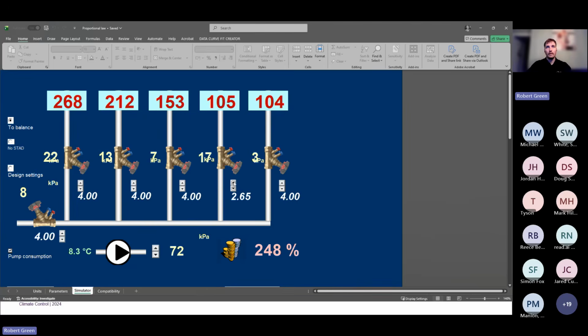Okay, I'm happy with that. 105 versus 104%. And now we're going to take this unit in the middle and restrict this unit down as well. What we're going to do is reduce it until these are the same. And if you look now, all three are the same. Turn this bit off. All three are the same, and these two have changed in proportion as I've done this change here.